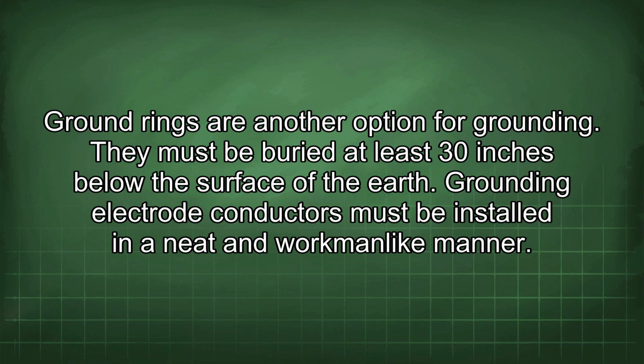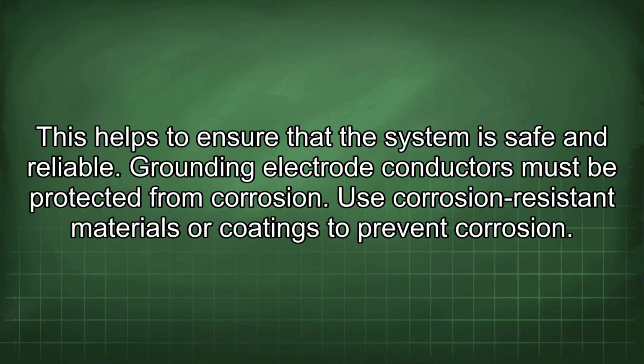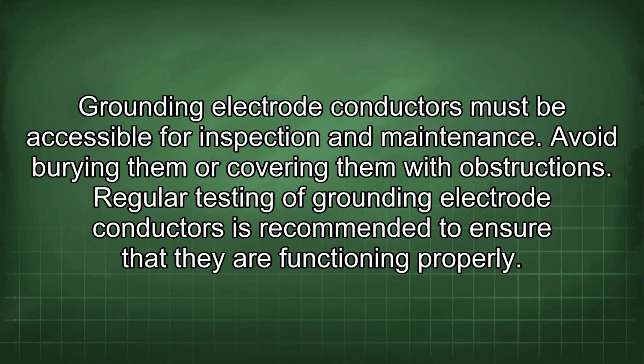Grounding electrode conductors must be installed in a neat and workmanlike manner. This helps to ensure that the system is safe and reliable. Grounding electrode conductors must be protected from corrosion. Use corrosion-resistant materials or coatings to prevent corrosion. Grounding electrode conductors must be accessible for inspection and maintenance. Avoid burying them or covering them with obstructions.